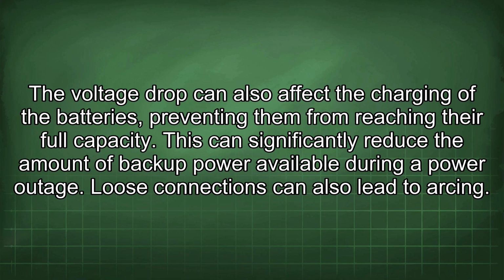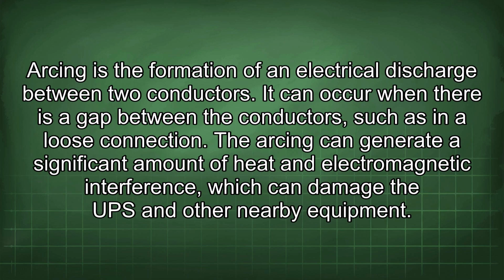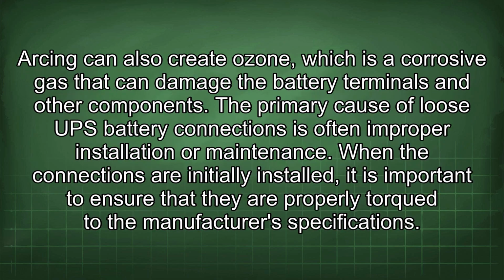Loose connections can also lead to arcing. Arcing is the formation of an electrical discharge between two conductors. It can occur when there is a gap between the conductors, such as in a loose connection. The arcing can generate a significant amount of heat and electromagnetic interference, which can damage the UPS and other nearby equipment. Arcing can also create ozone, which is a corrosive gas that can damage the battery terminals and other components.